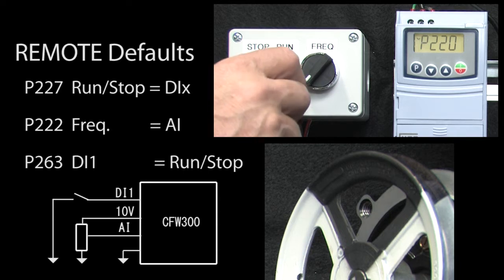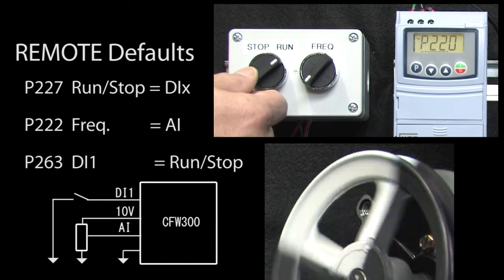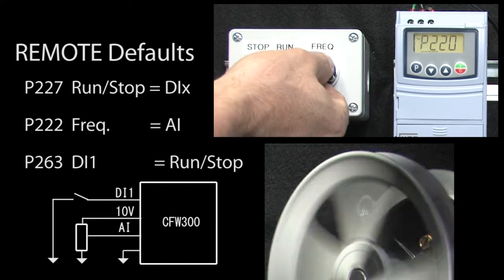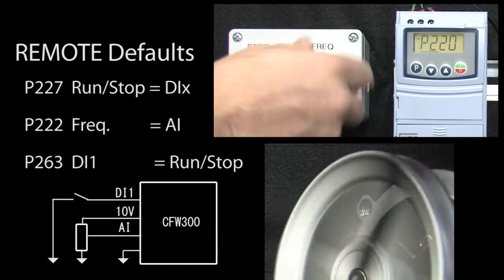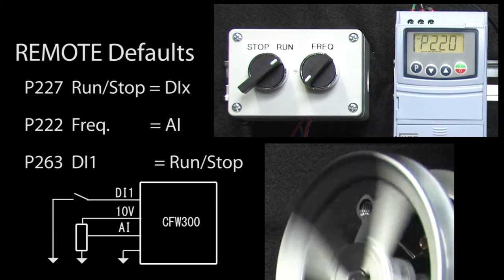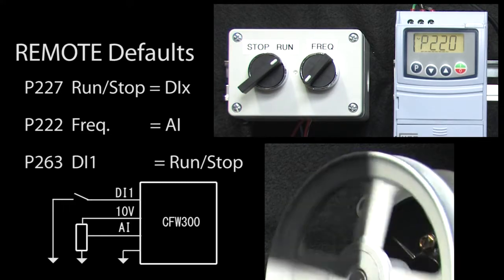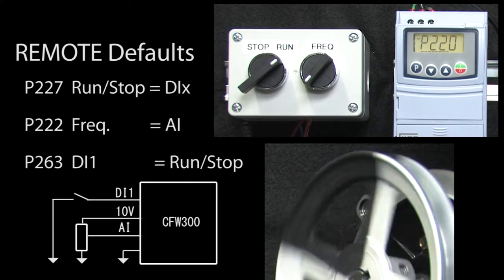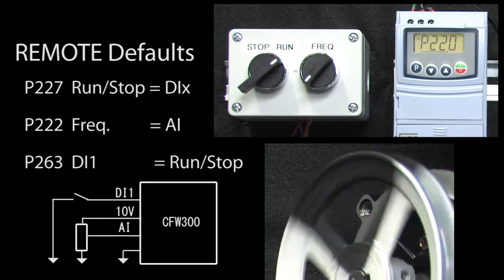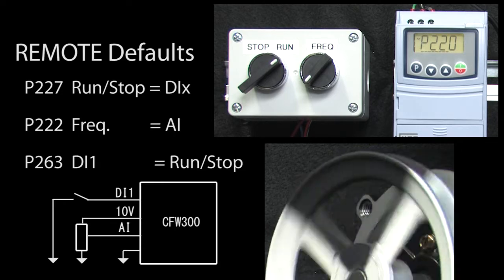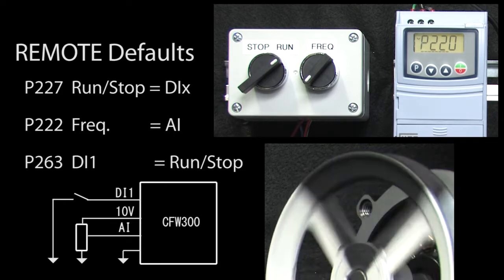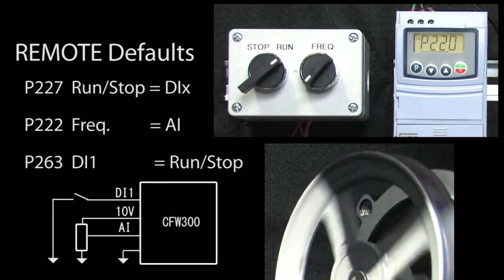So, if I flip the switch to run and vary the potentiometer, sure enough the drive responds. And since all the parameter values we needed were the factory default values, we didn't have to change any parameters after we changed the remote mode to use this digital and analog input.